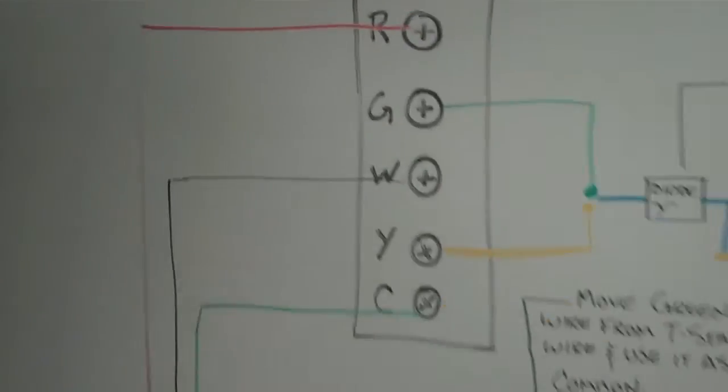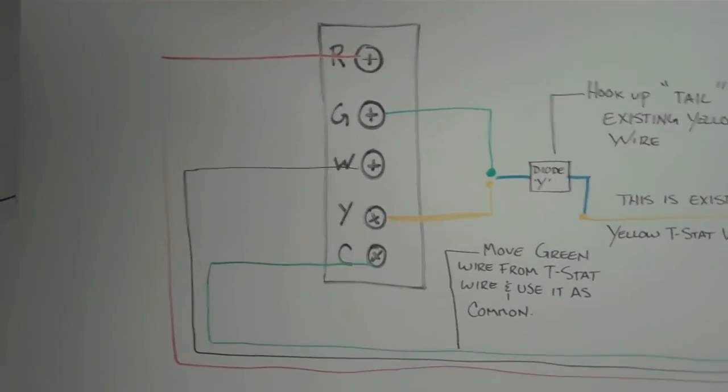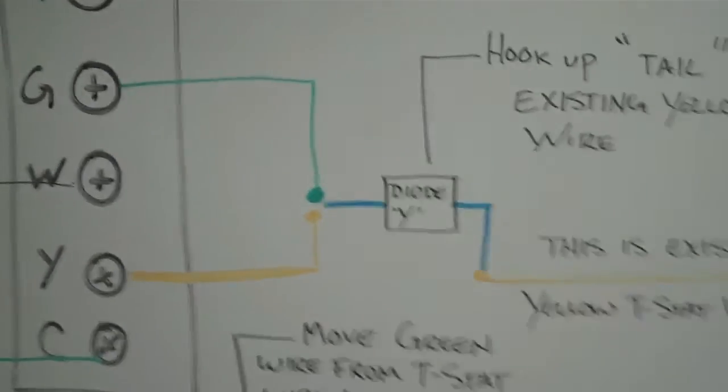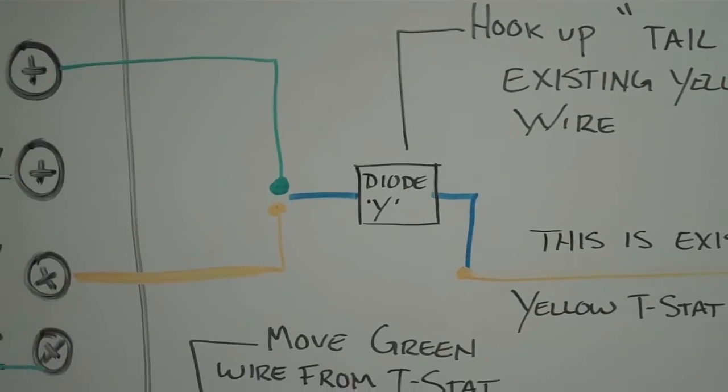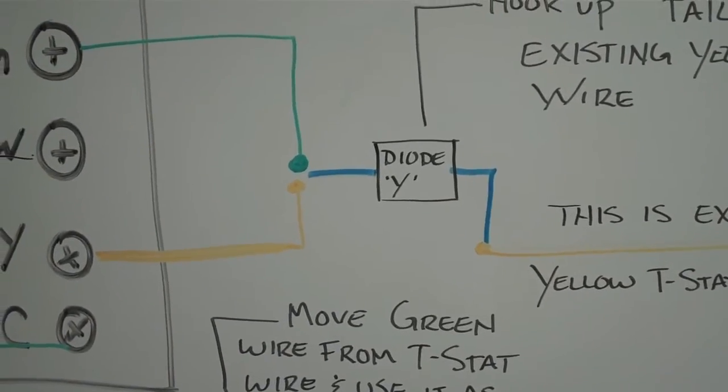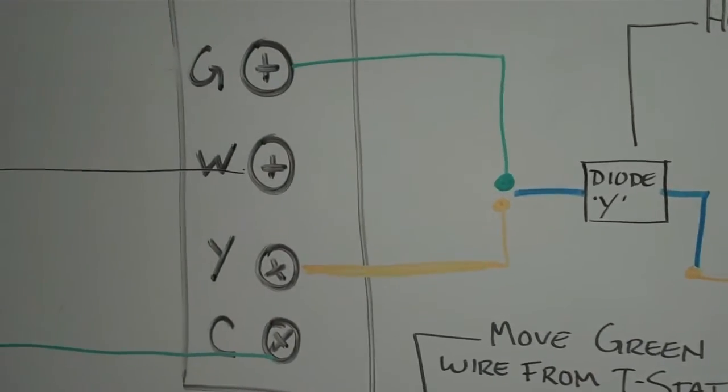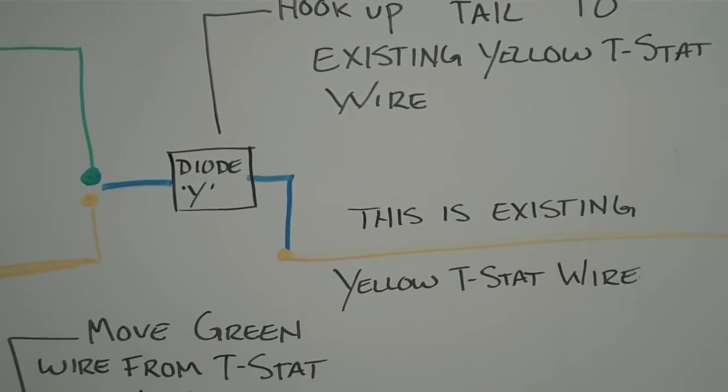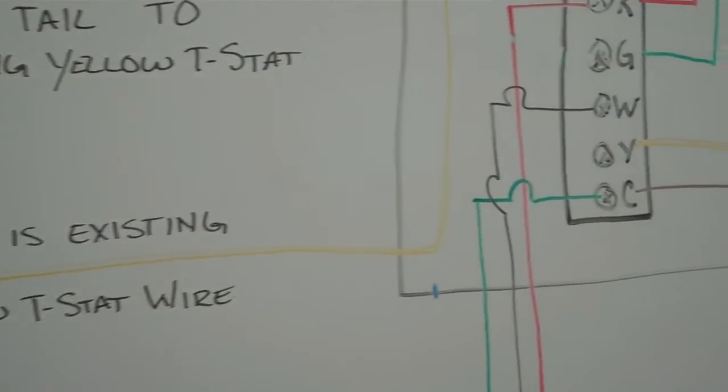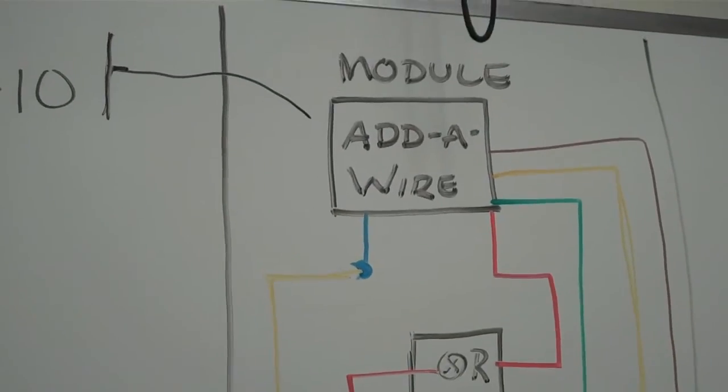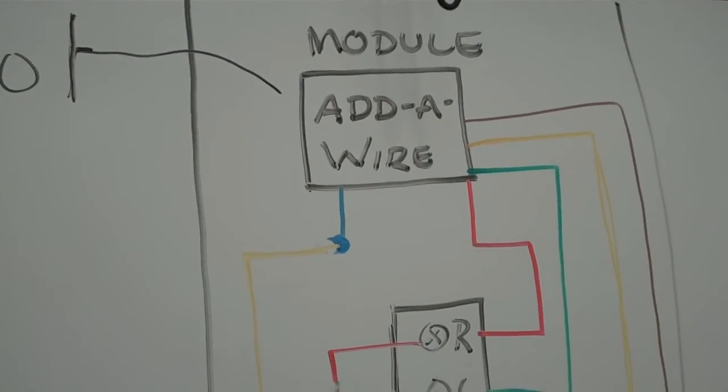So what this allows you to do is take a normal thermostat that has four wires, and they give you a diode Y. They supply you with a lead that comes off that has a yellow and a green. It goes back with a blue tail after the diode that you can replace the green and the yellow on your thermostat with, and then use that wire that comes off of it to go back to the furnace air handler and tie into the module that gets installed in the furnace.